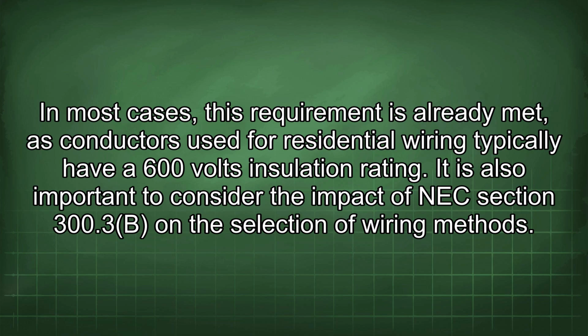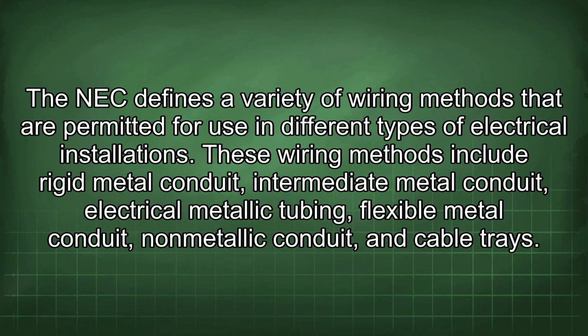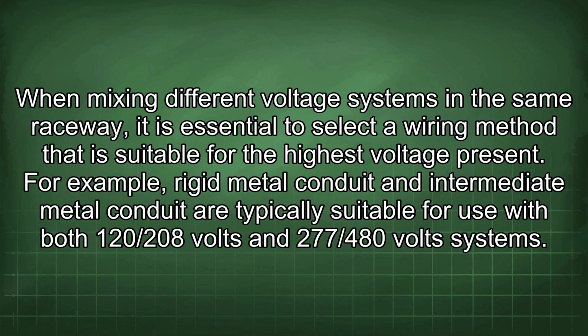It is also important to consider the impact of NEC Section 300.3b on the selection of wiring methods. The NEC defines a variety of wiring methods that are permitted for use in different types of electrical installations. These wiring methods include rigid metal conduit, intermediate metal conduit, electrical metallic tubing, flexible metal conduit, non-metallic conduit, and cable trays. When mixing different voltage systems in the same raceway, it is essential to select a wiring method that is suitable for the highest voltage present.